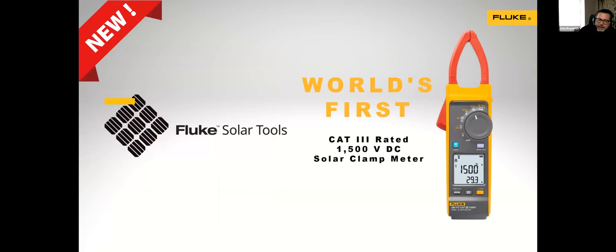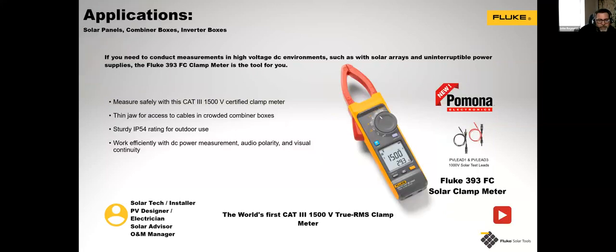So about 18 months ago, this was the first Cat3 1500 volt rated DC clamp meter. As time has gone on, the competitors have realized that there is a market there, so there are others available. But the advantage of what Fluke are doing, you get the traditional Fluke build quality, safety inbuilt with the Cat3 1500 volt rating. It will give you all of the Pomona test leads. It's got a thin jaw for access to cables in crowded combiner boxes, standard IP rating of 54, and because it's FC, you'll be able to transmit any readings that you get, both to the tester itself and also to your mobile phone.